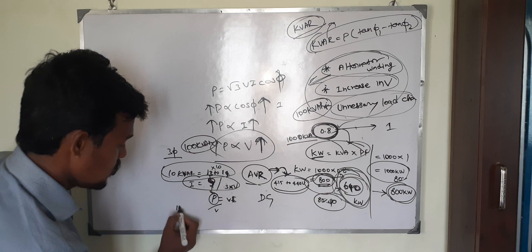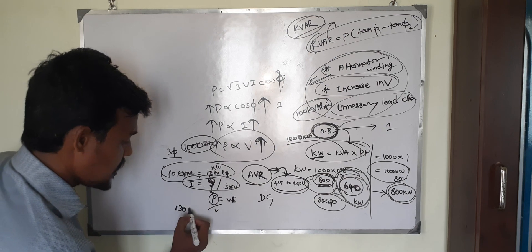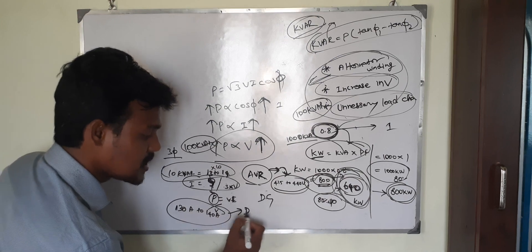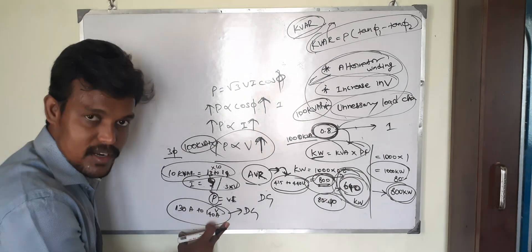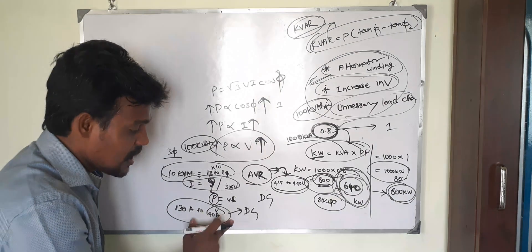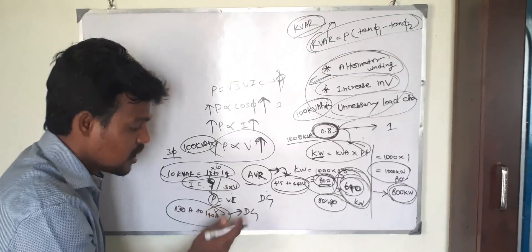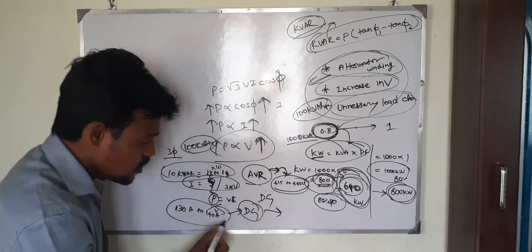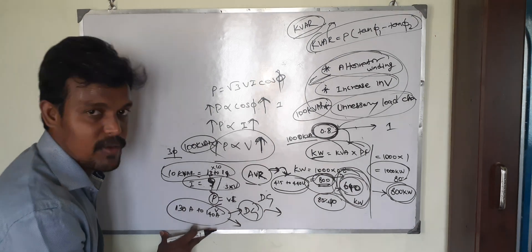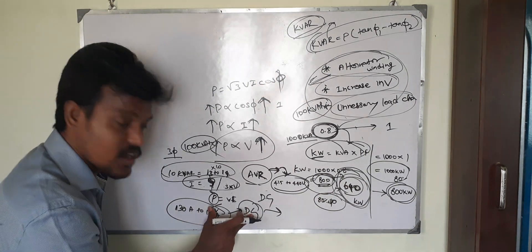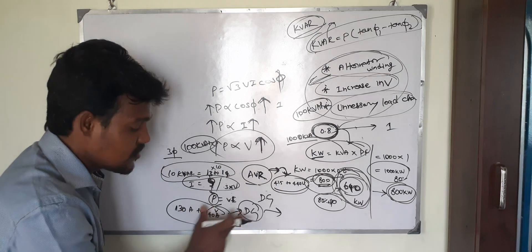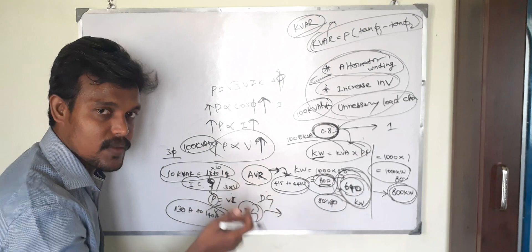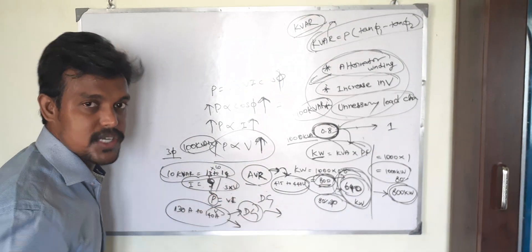This sudden load increase from the capacitor bank is not real power — it is reactive power. That is the problem. If you want to utilize your DG efficiently for your actual load, you have to cut out this reactive power. Otherwise the DG is unnecessarily running for reactive power and your diesel consumption will be higher compared to regular consumption.